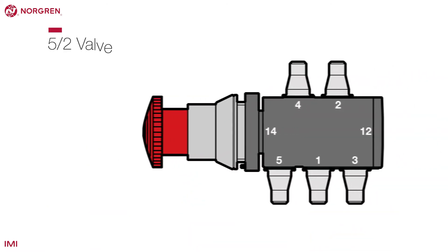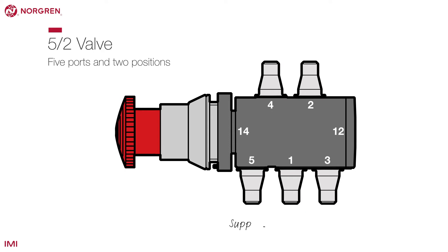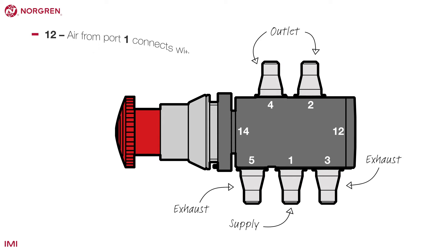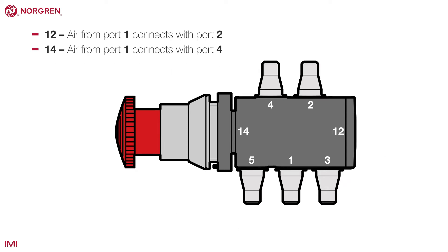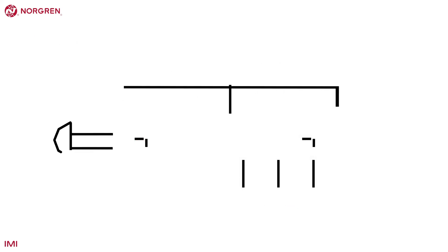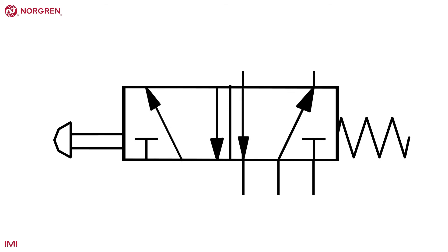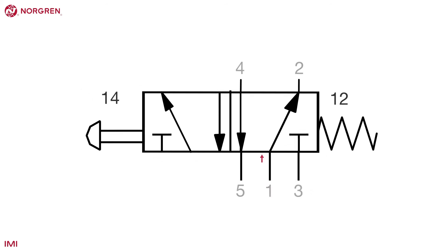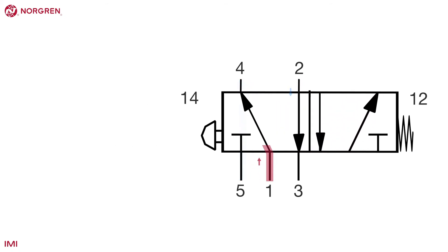A 5-2 valve has 5 ports and 2 positions. There is still 1 inlet, but now there are 2 outlets and 2 exhausts. The 2 positions are air to port 2 outlet or air to port 4 outlet, so the operation for this valve would be 1-2 and 1-4. When the air flows to port 2, the air from port 4 passes to the exhaust. When the air flows to port 4, the air from port 2 passes back through the exhaust.